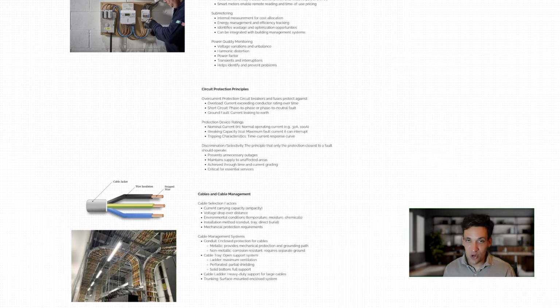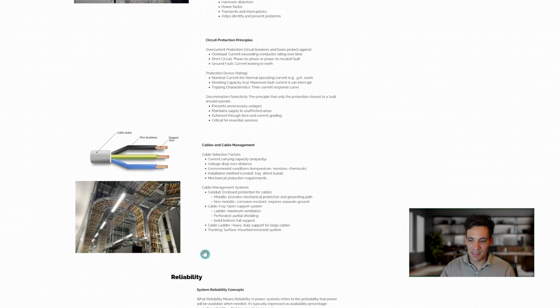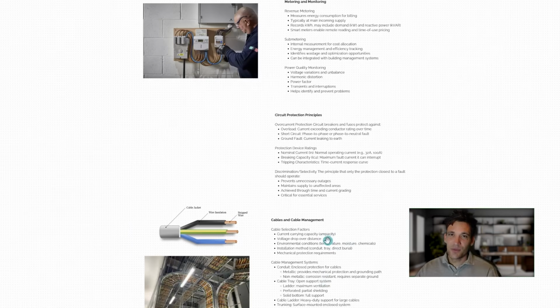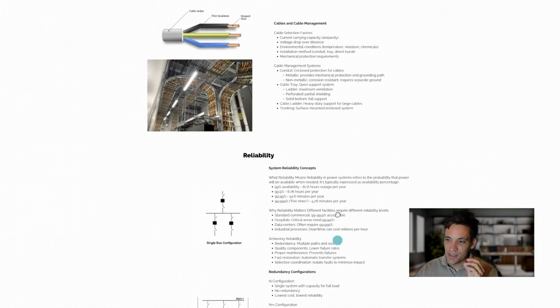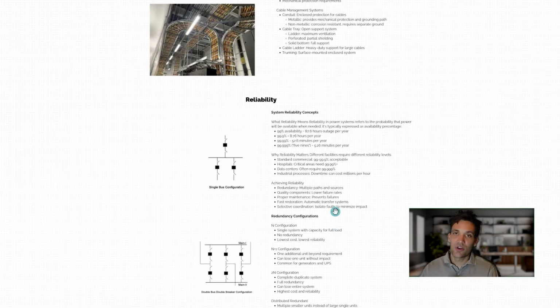Cables can either run in conduits, which are plastic tubes that you can either install above ground or bury below the ground, or in cable ladder or cable tray, which is open metal baskets like this that the cable sits on. Fundamental to the design of any electrical system is this concept of reliability. Yes, the cost of a system, the design you choose, varies significantly on the amount of connected load. That's probably the biggest factor, but after that, the next big one is the reliability you want the system to have. Does it have to be reliable 90% of the time, or does it have to be reliable 99.99999% of the time? Because that's going to inform major design and architecture decisions.